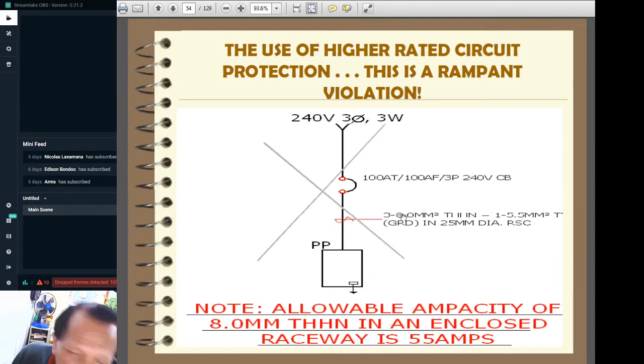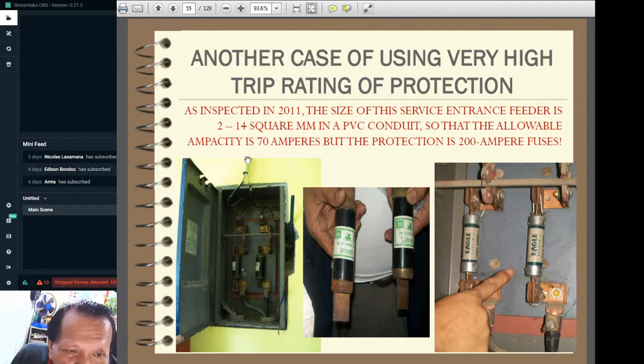So this is for practitioners. Sometimes many practitioners are really not knowledgeable and make a mistake of providing circuit breaker protection trip settings that are higher than the correct values. So this is an example, and this is an example again. There is this feeder wire coming in to the fuse disconnect switch, but the fuse is very high, 200 amperes, as against the ampacity of the wire. The capacity of the wire is only good for 70 amperes, but the fuse is 200 amperes. So there's a possibility of overloading the wire because the protection is too high. The protection should be equal or almost equal to the ampacity of the wire.